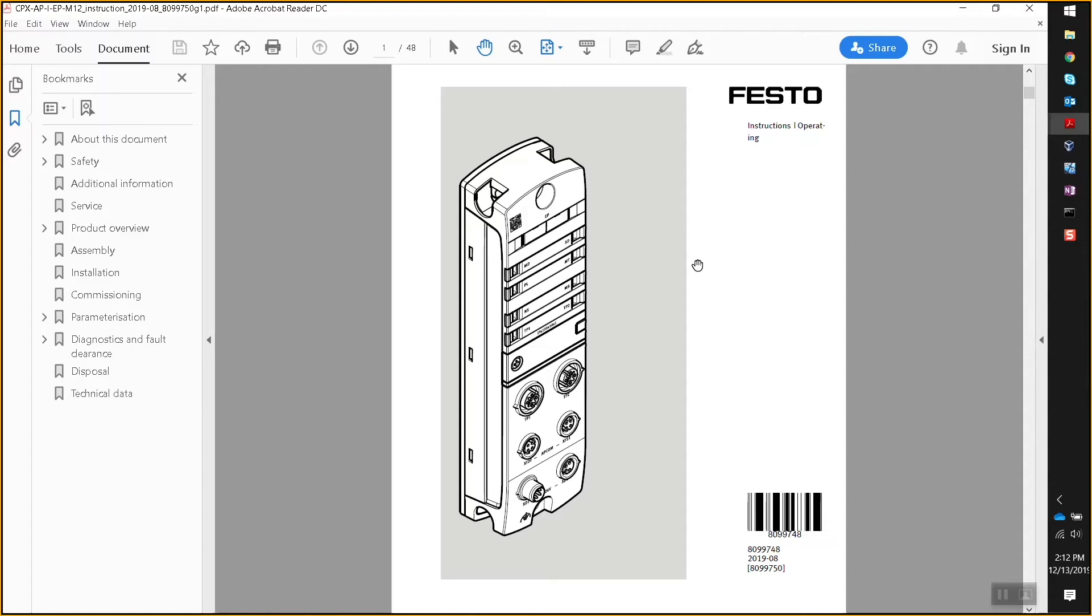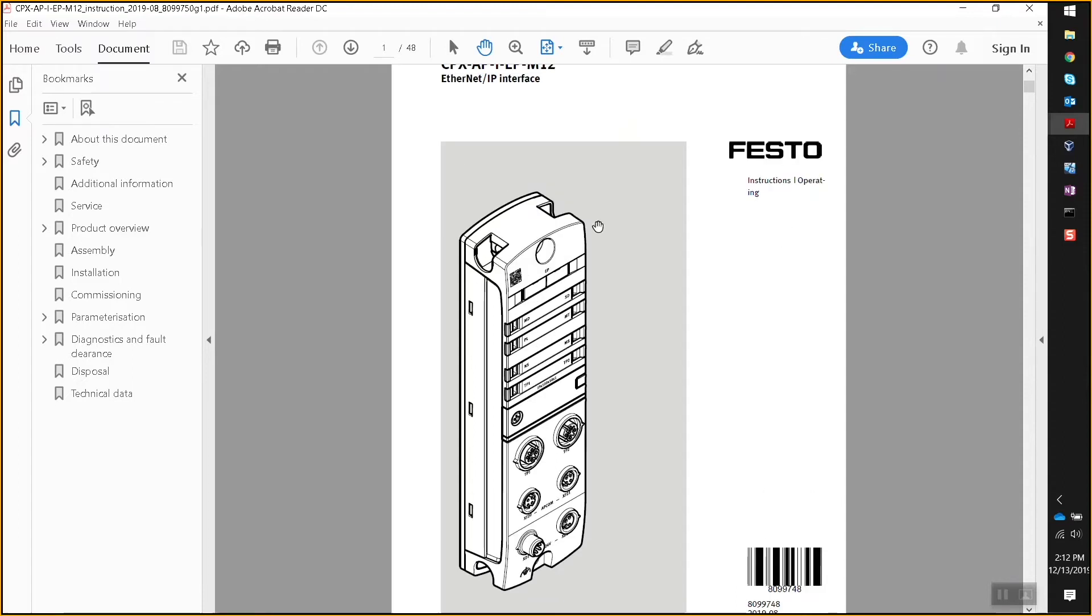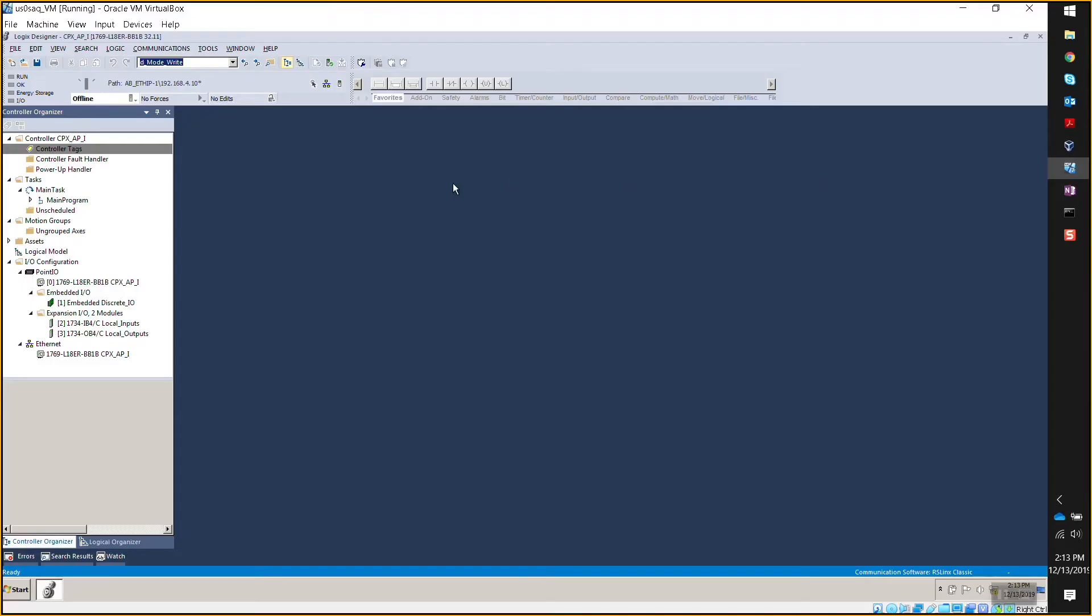It is out of the box. I was reading through the manual and I noticed that out of the box it starts as DHCP, right? Well, that's correct. That's an ODVA requirement and all of our devices are DHCP out of the box. It should be pretty easy to set the IP address though. You could use Rockwell BootP for starters. Okay. I would start with that. Okay. Yeah, we can do that. Let me start BootP then.